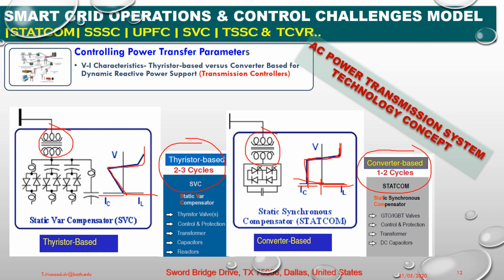Okay. In other words, the SVC, being composed of thyristor switched capacitor and reactor, becomes a fixed capacitive admittance at full output. That is the main difference. Eventually, the maximum attainable compensating current of the SVC decreases linearly with the AC system voltage, and the maximum VAR output decreases with the square of this voltage.